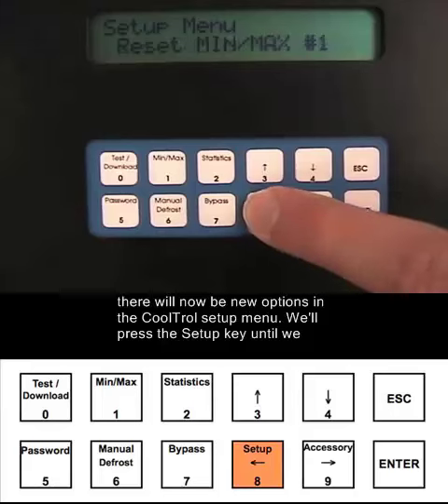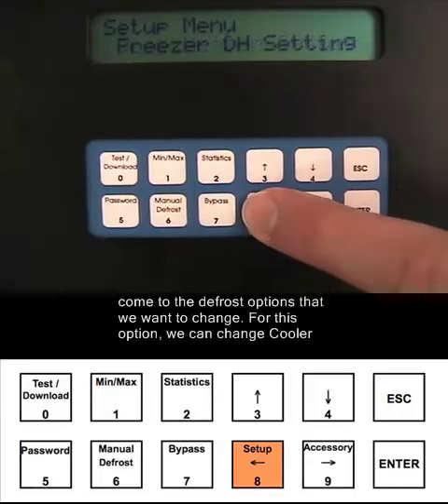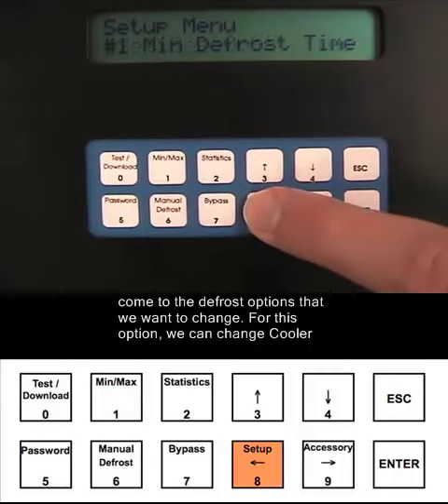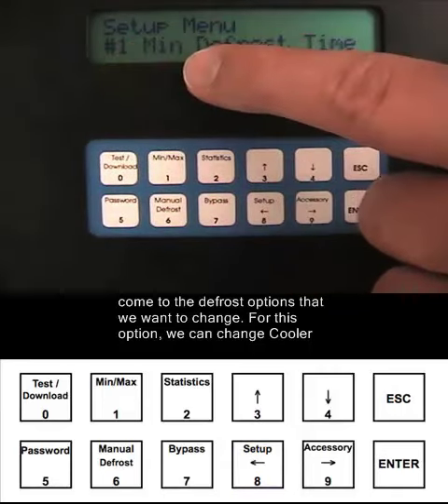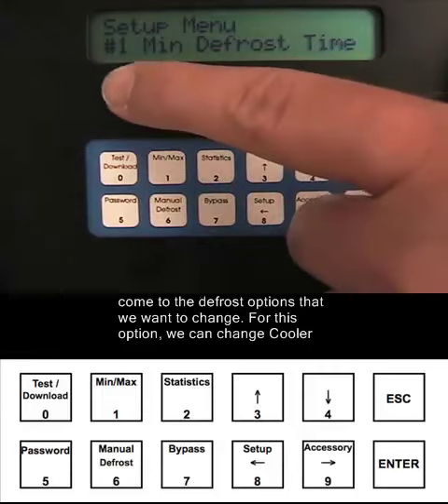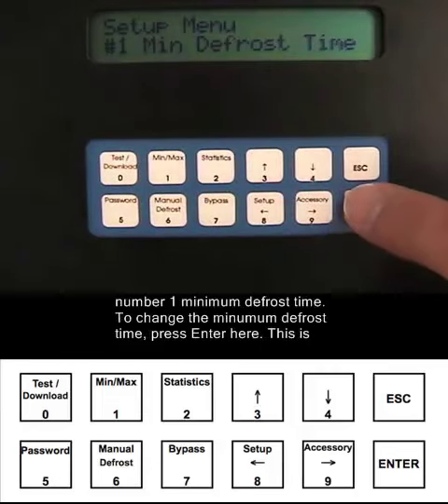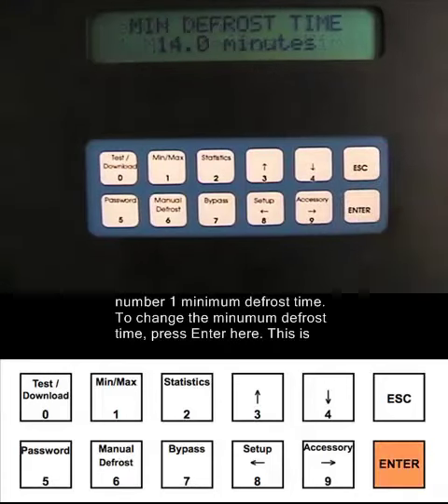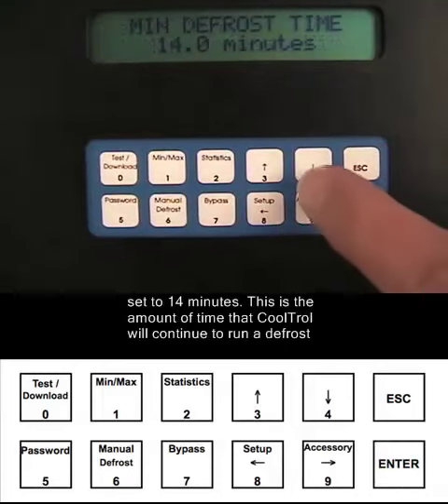We'll press the setup key until we come to the defrost options that we want to change. For this option, we can change cooler number 1 minimum defrost time. To change the minimum defrost time, press enter here. This is set to 14 minutes.